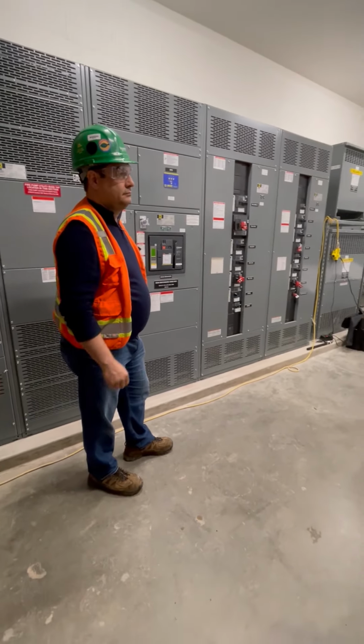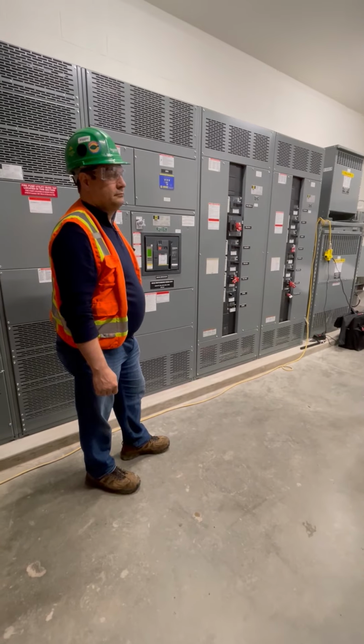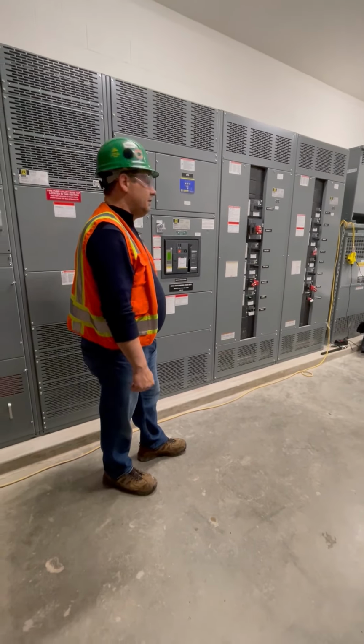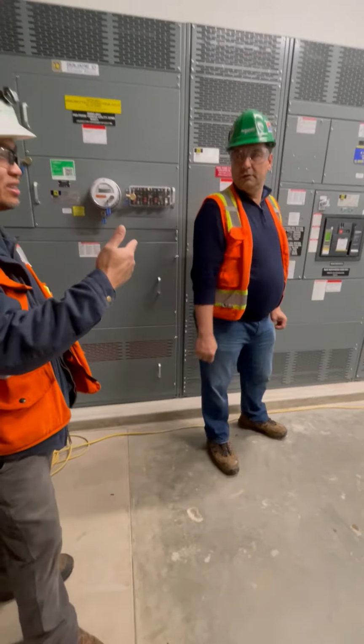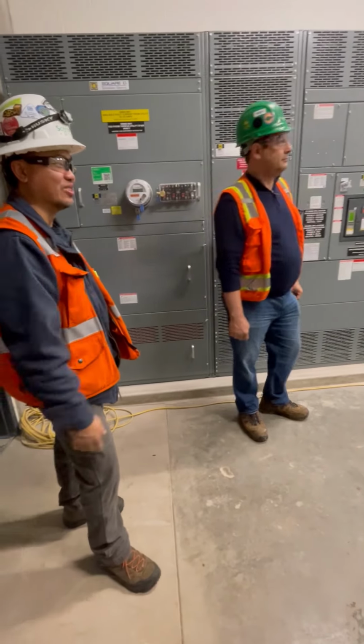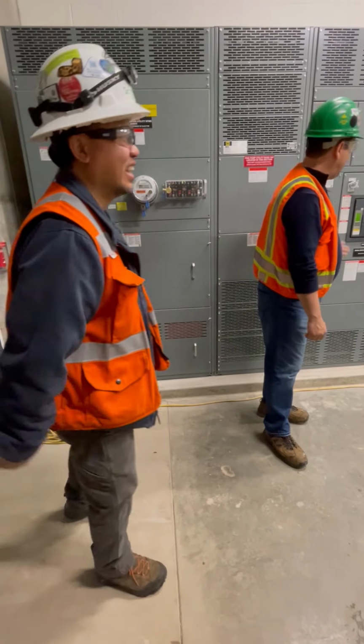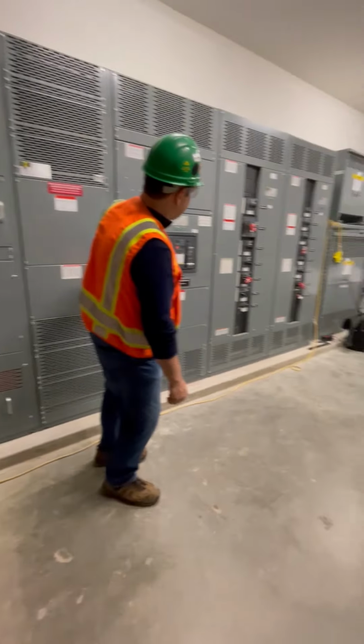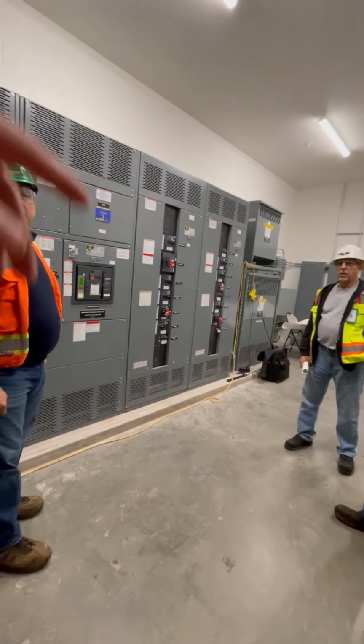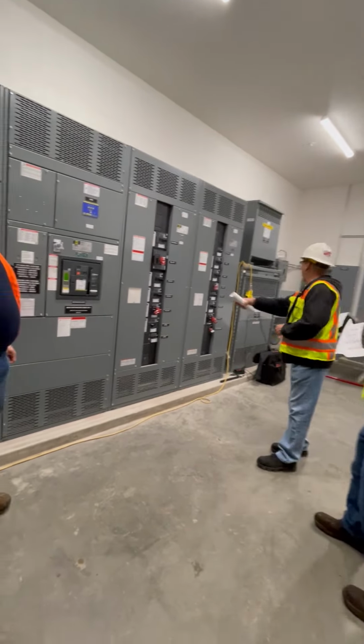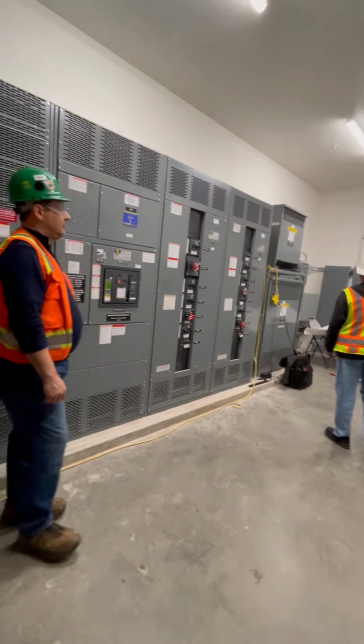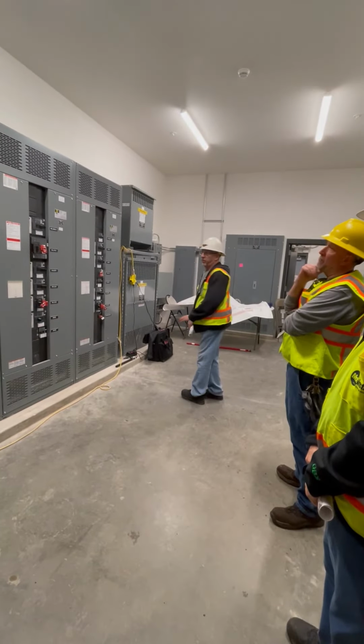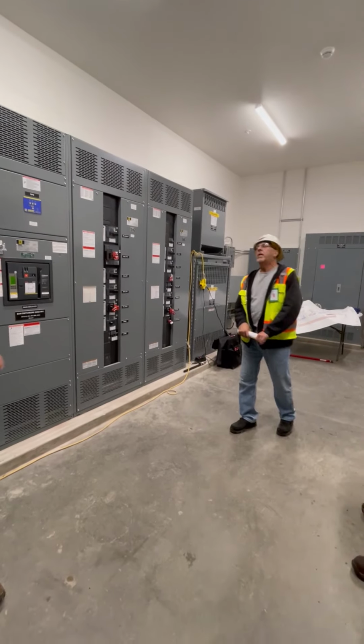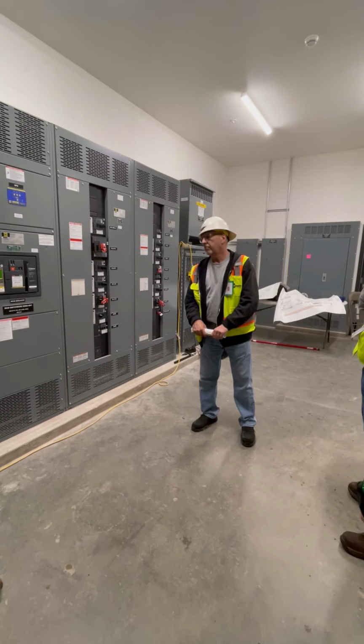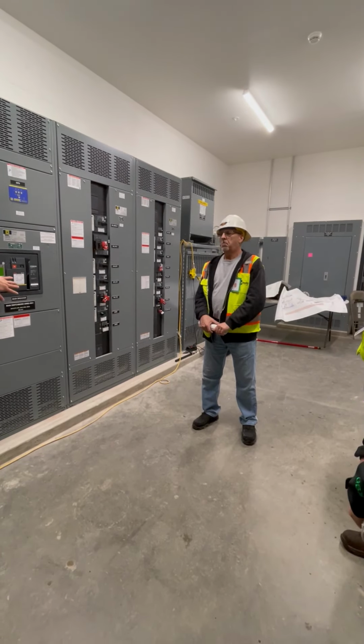But we've got a generator firing up and everything else happening. If your generator fires up and starts powering this, it's going to trip again, even if you close it. Doesn't matter, right? But do you have a generator backfeeding it? I don't see one, so you must have an ATS. The generator backfeeds a fuel emergency pump. Ah, so you've got an ATS downstream, so you don't have to worry about the generator tripping this one.